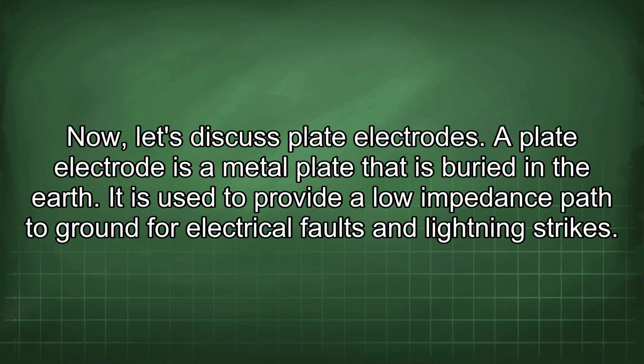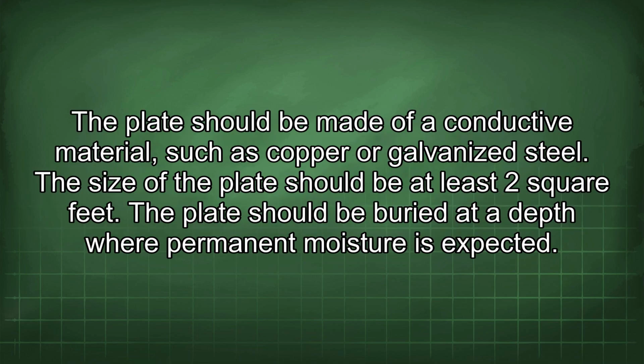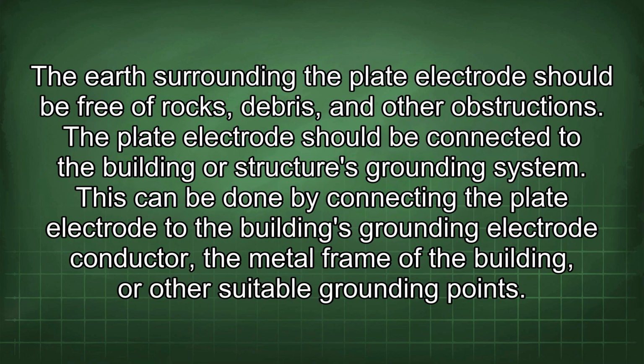Now let's discuss plate electrodes. A plate electrode is a metal plate that is buried in the earth. It is used to provide a low impedance path to ground for electrical faults and lightning strikes. The plate should be made of a conductive material such as copper or galvanized steel. The size of the plate should be at least 2 square feet. The plate should be buried at a depth where permanent moisture is expected. The earth surrounding the plate electrode should be free of rocks, debris, and other obstructions.